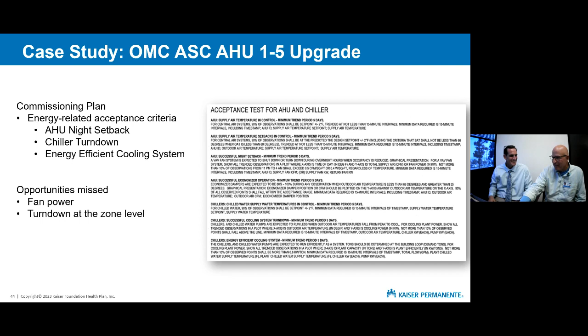We got a report and they said, well, chiller power wasn't available. And they also said, well, facilities would not let the night setback scheme work. They locked it out, so we couldn't validate it by trending. And we discovered, like I said, chiller power was unavailable. So we added a power meter and lo and behold, this is what we got. And as you can see, we're well above 0.8 kW per ton.